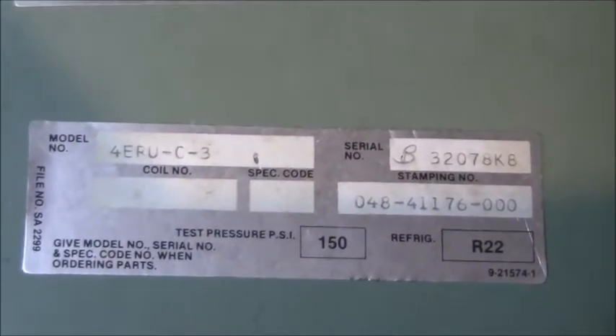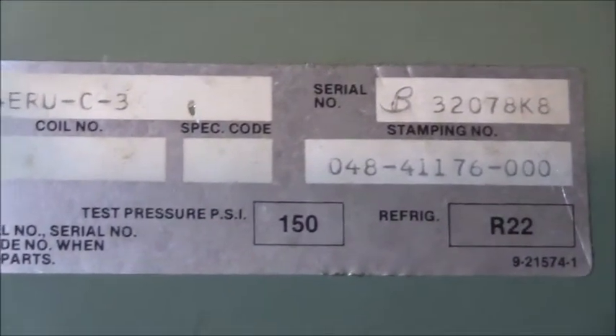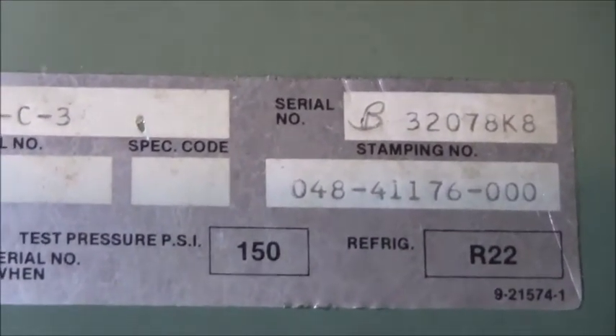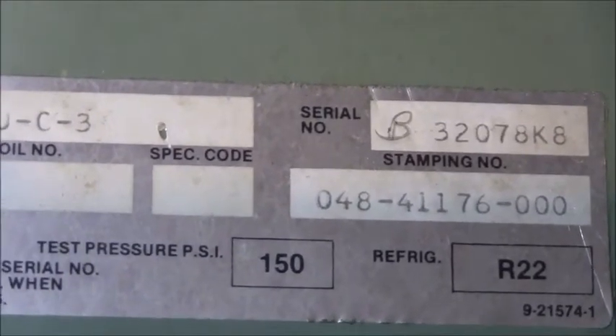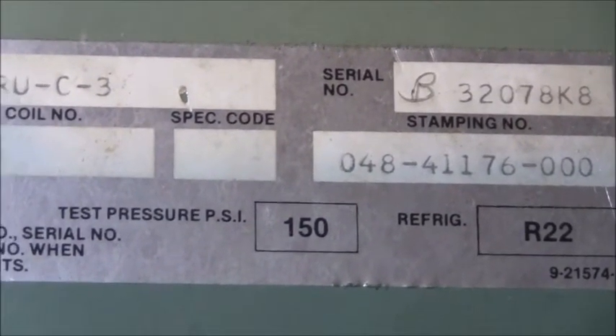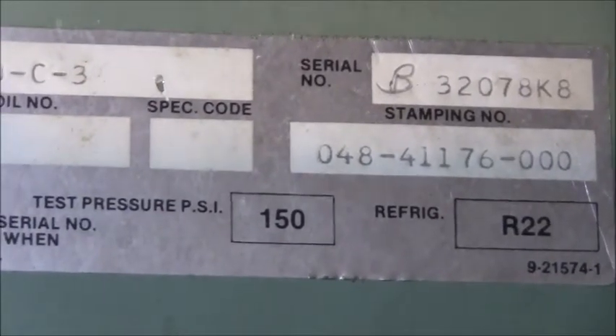Now let me just show you a little bit. Okay, so when you look at this number here, 048, each ton of air conditioning is 12,000 BTUs per hour. So when you normally see a number like 048, you take that number and divide it by 12, and you're going to come up with 4 tons. So there's a high probability that this unit is a 4-ton unit. So there's your AC tonnage.